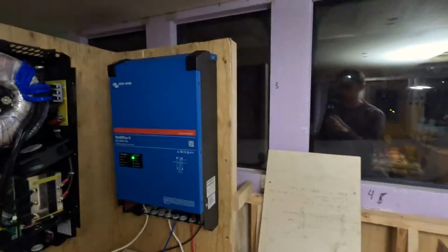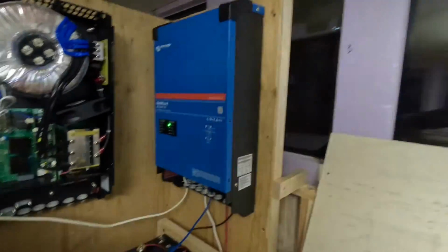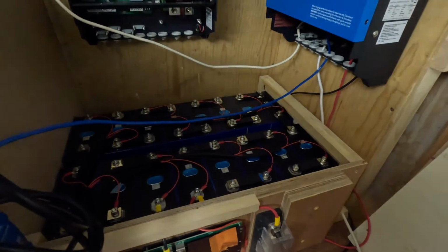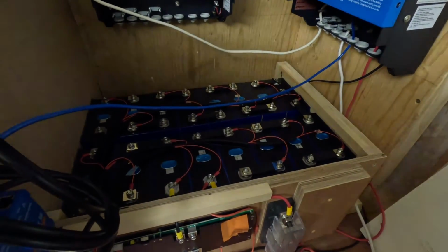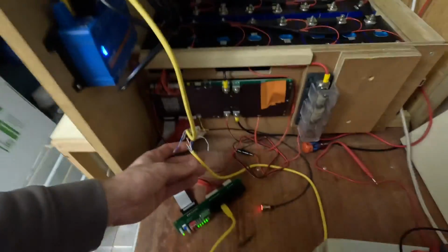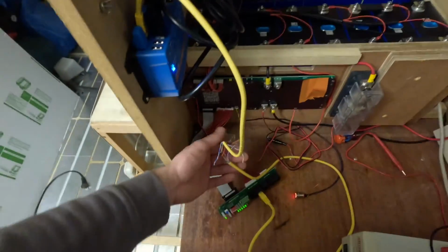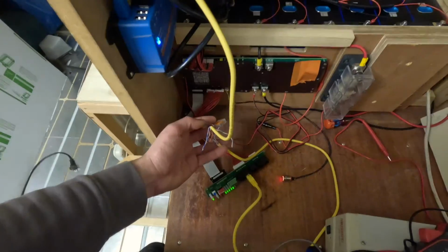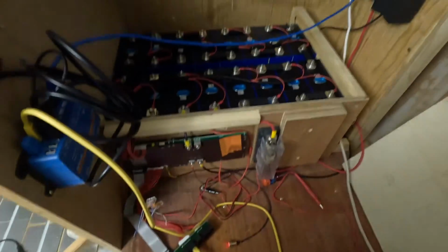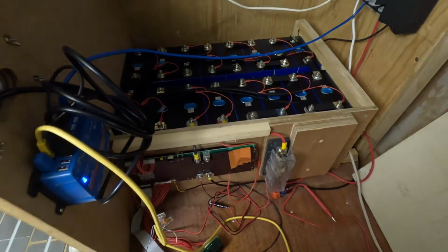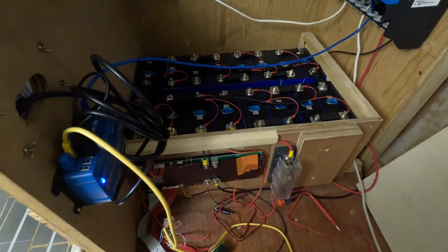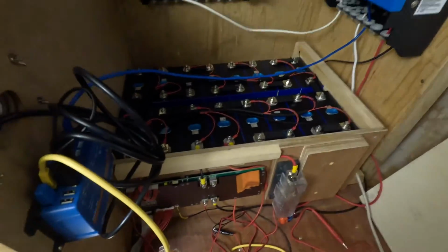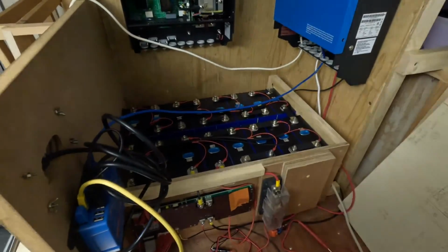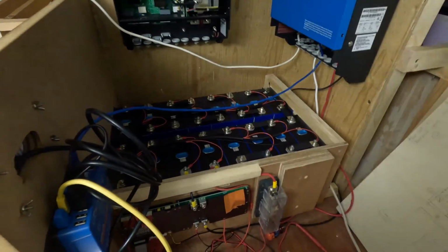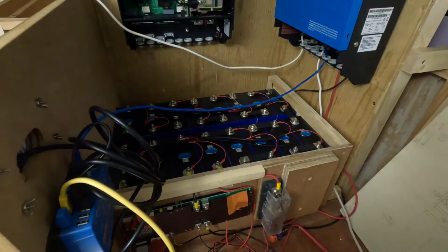Right now it's only one multiplus, so it's quite easy, but for example later on if we would have solar and a multiplus and a lot of things, then that should be sorted out by the Cerbo GX in the Victron system. And this communication goes over the CAN bus, very, very hacky right now on a standard LAN cable, but yeah, this will obviously be sorted out later. Next step here is to actually also start to sort out some better cabling, because now it's just a mess. And the whole idea with this mock-up setup is that we should be able to do all the cabling here now, nice and tidy. So it's just a matter of installing it in the boat later on when we get to that boat.